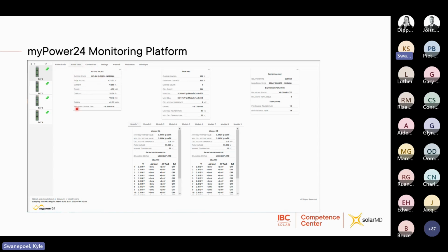And here we can get a status overview of what's happening with this specific battery. Number 2, we can see that that relay is closed, and this is the current pack voltage. It has a current, a positive current, so it is busy charging. And this is the power, which is calculated based on the voltage and current. And the capacity on that battery is 32%. So at this rate, the battery will take 21 hours to charge. This is just a 1-minute data point that we use to calculate how long it will charge based on the average of this current.